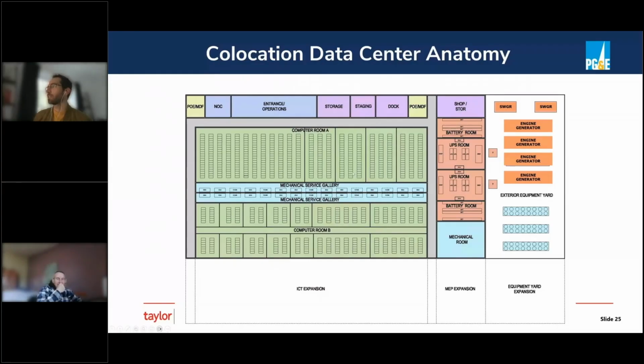Instead, this engineer very likely used the underfloor as a means for distributing electrical out from the main electrical rooms to the computer rooms, where they're likely hitting power distribution units before going out to the servers. On the far right, in this case, you see we have another generator yard and some air-cooled chillers. There's an indoor mechanical room as well. Again, battery rooms and UPS room, that point of entry for where the telecoms are coming in, the NOC, and the operations center for the operators. So more or less the same things, just oriented in a slightly different way.